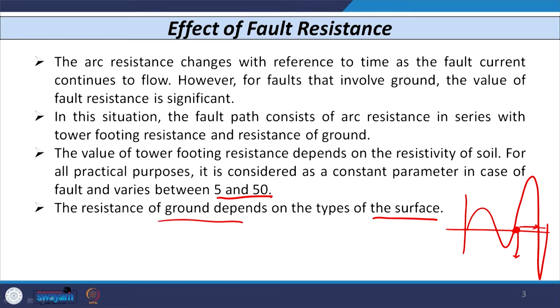Now, in this situation, the fault path consists of arc resistance along with some tower resistance and resistance of ground. For all cases, the tower resistance is fixed and it varies from 5 to 50 ohm. It is proved, and some empirical formula is also available, that the value of tower resistance varies from 5 to 50 ohm. So, that we can consider. The resistance of ground depends on what type of surface we are using, whether RCC surface, plane surface, asphalt surface or some other type of surface, then the value of the ground resistance also changes. So, we need to take all these points into account when we consider the impact of fault resistance.